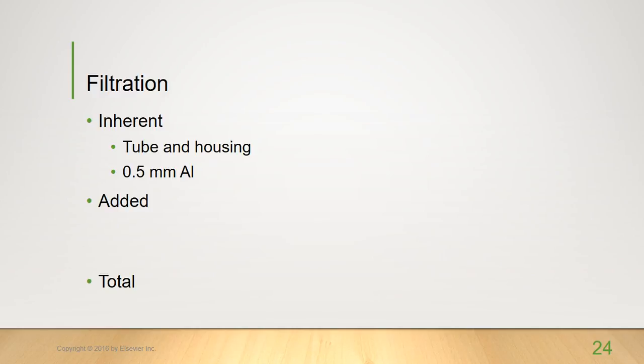And then in general radiography, the tube head assembly, added filtration is something else. This is another 2 millimeters of aluminum that's placed between the target window and the top of the collimator. So where the window is and where it comes out of the collimator is called added filtration, and the purpose of that, very important for you to know, is to remove low energy X-ray photons from the beam before they can expose the patient and contribute to dose instead of an image. So know that added filtration is used to remove low energy X-ray photons.